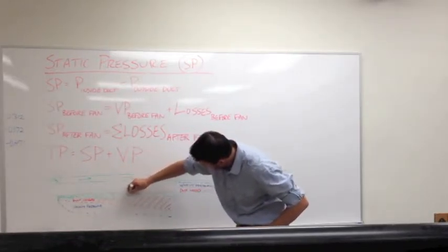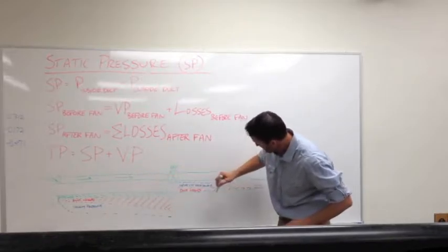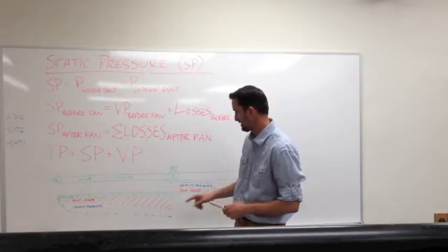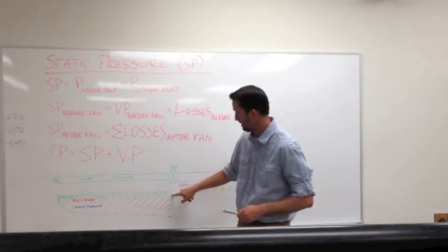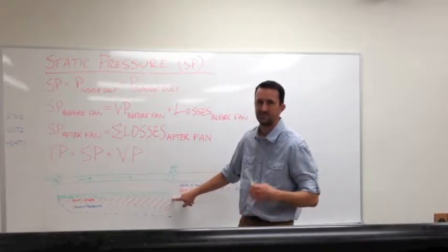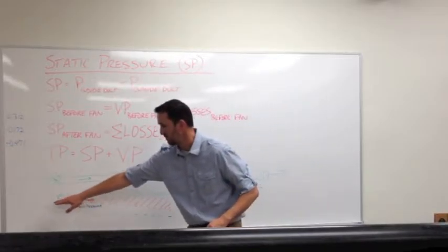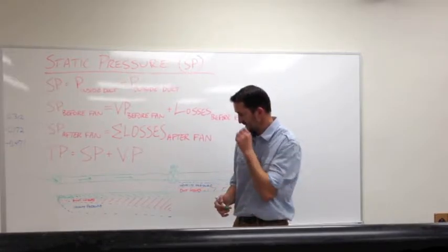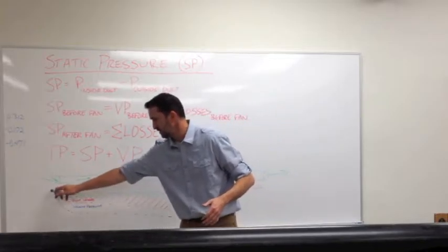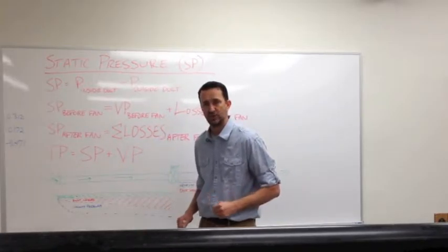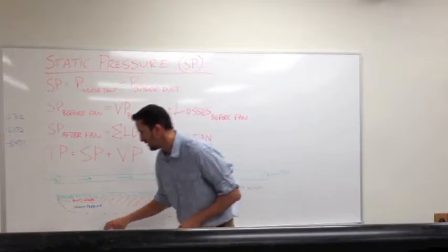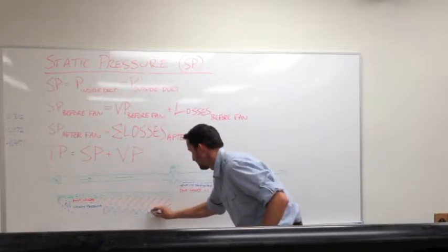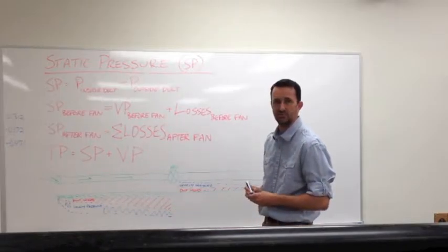And we can hash that in this way, right? So the green portion there represents the amount of pressure that the fan had to use up to overcome that entry, the air to get into the duct. Once the air is in the duct, we also had to convert that static pressure to velocity pressure. Okay? So now the blue section right here represents the velocity pressure. Okay?